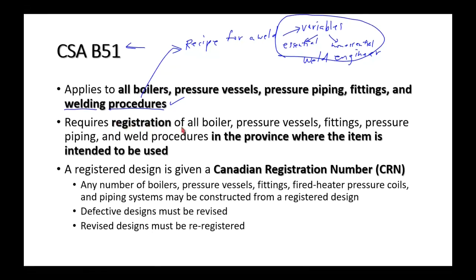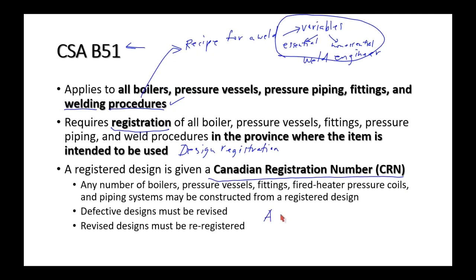CSA B51 says that boilers, pressure vessels, and pressure piping must all be registered designs. Every boiler and pressure vessel has a CRN — a Canadian Registration Number — for example, A1227.5123. These are basically catalog numbers unique to a particular design.